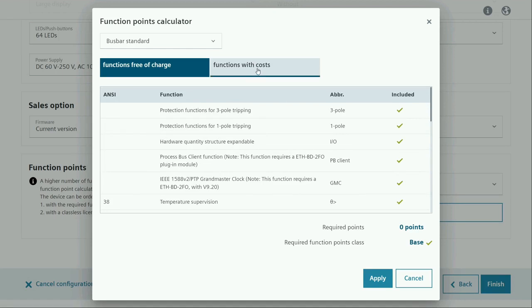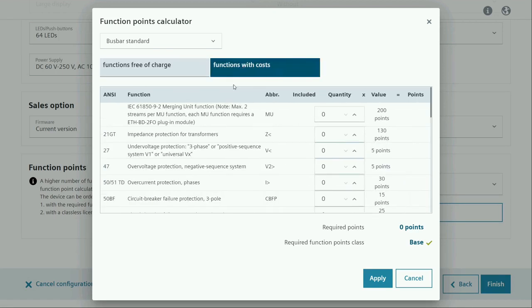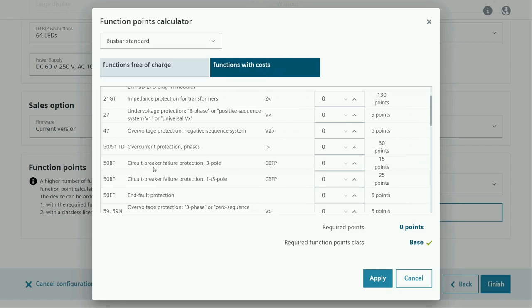Okay, and now we jump to the functions with costs. Here you really have the option to make clear what functionality you want to put in the device. Do I need, for example, a backup overcurrent protection? Then you can increase the number here. In our case, I'm of course interested in the circuit breaker failure protection, 3-pole. We take this 4 times for all of the 4 feeder bays, increasing the number up to 60 points. And down there you always see an overview of how many function points are needed overall.